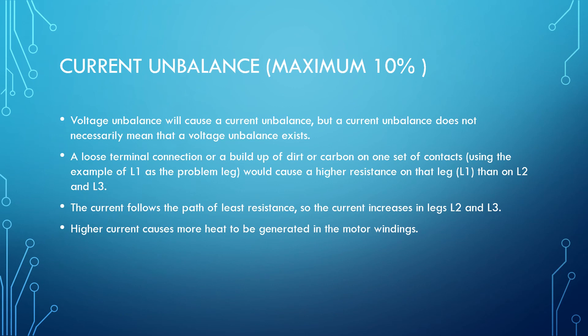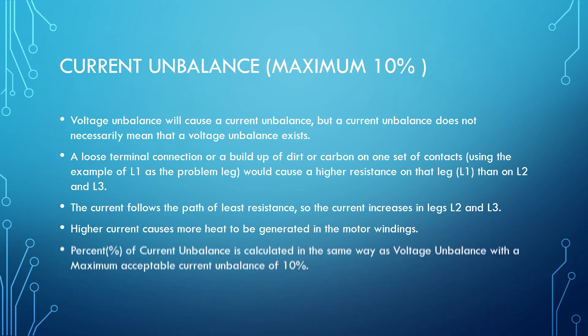Higher current causes more heat to be generated in the motor windings. Percent of current unbalance is calculated in the same way as voltage unbalance, with a maximum acceptable current unbalance of 10%.